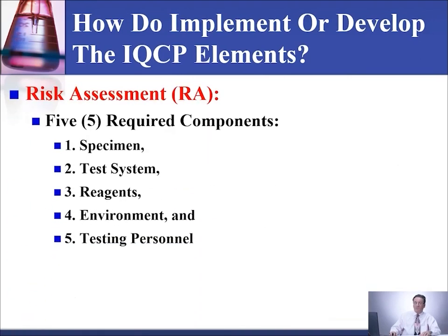So we said each IQCP element must be evaluated using the 5 required components in the 3 stages of testing: pre-analytical, analytical, and post-analytical.